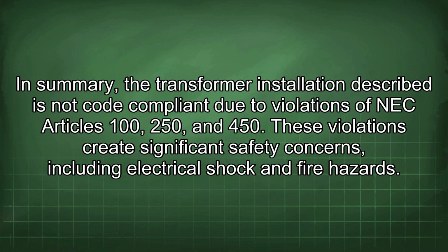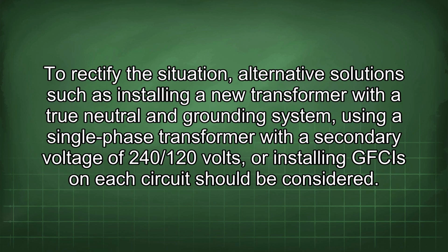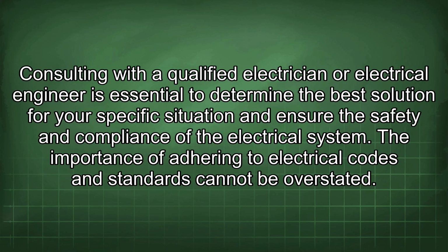In summary, the transformer installation described is not code compliant due to violations of NEC Articles 100, 250, and 450. These violations create significant safety concerns, including electrical shock and fire hazards. To rectify the situation, alternative solutions such as installing a new transformer with a true neutral and grounding system, using a single-phase transformer with a secondary voltage of 240/120 volts, or installing GFCIs on each circuit should be considered. Consulting with a qualified electrician or electrical engineer is essential to determine the best solution for your specific situation and ensure the safety and compliance of the electrical system.